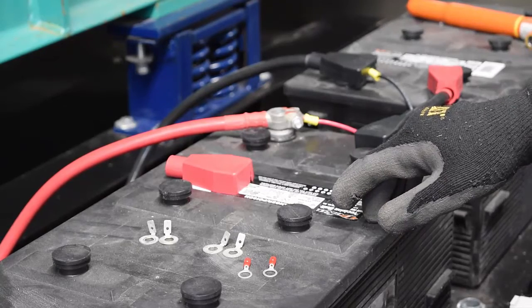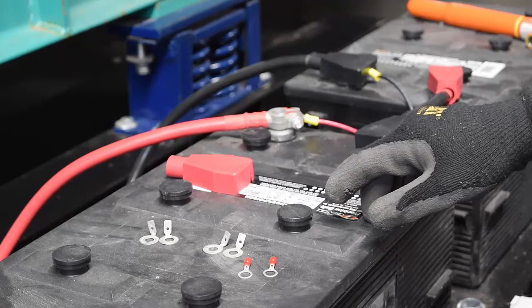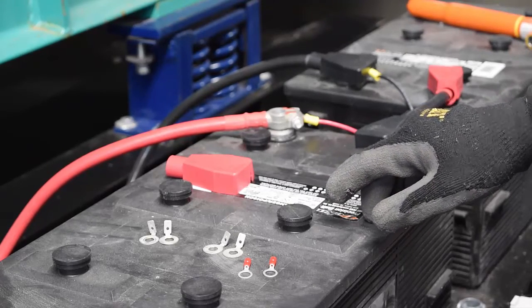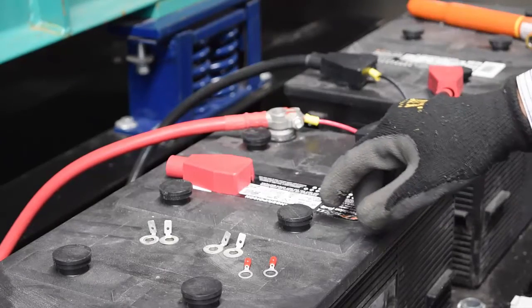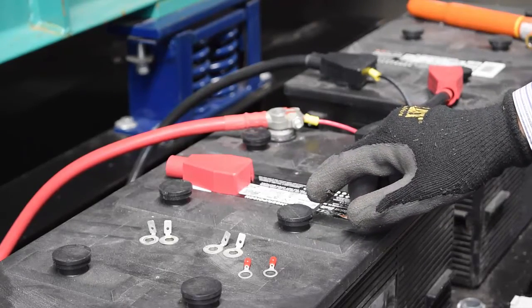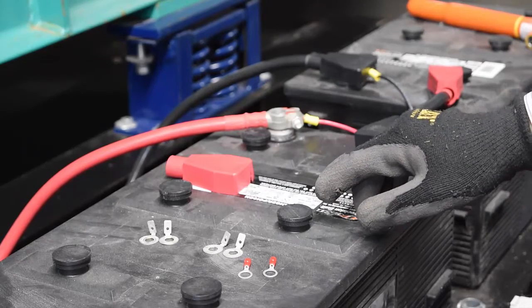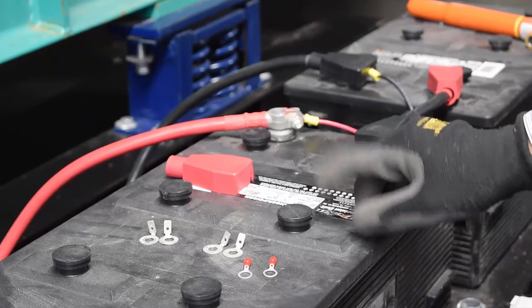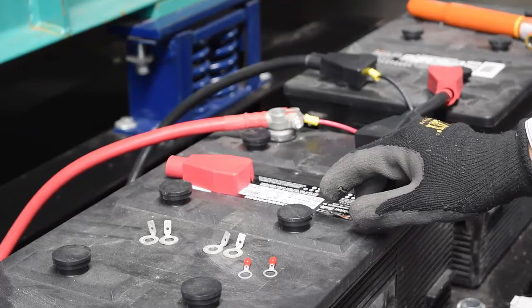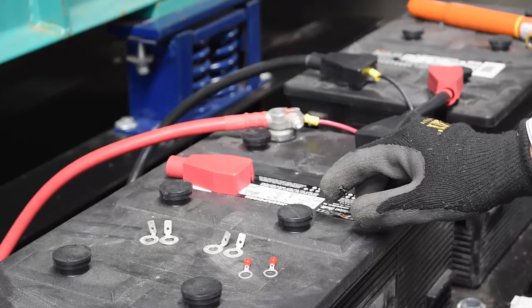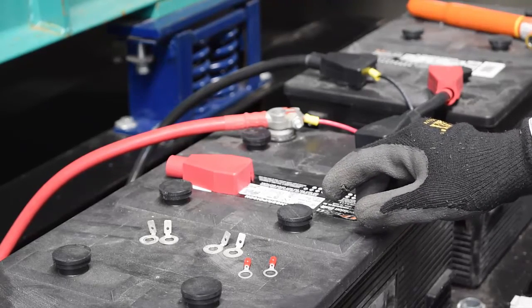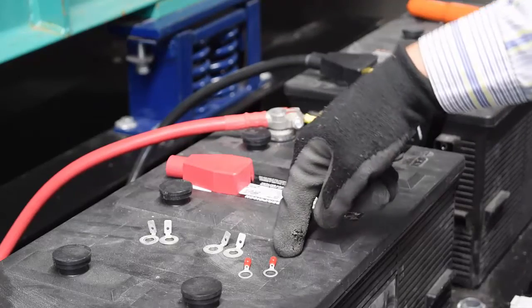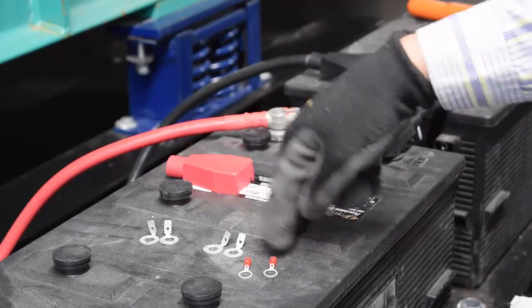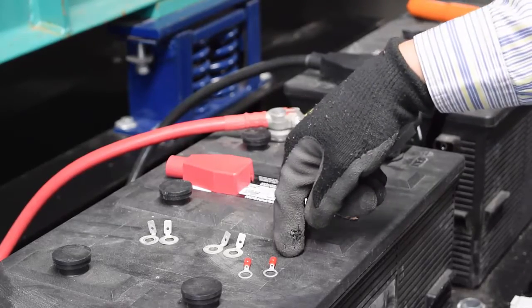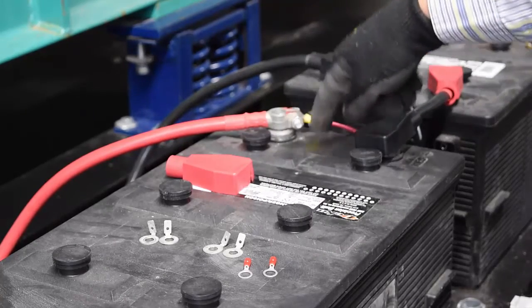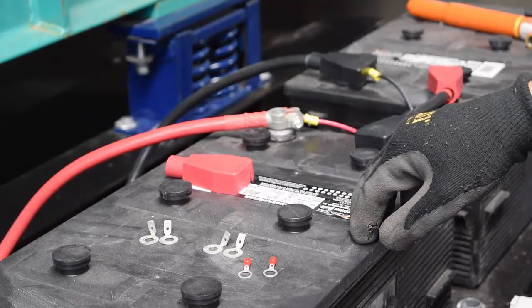If your system includes a BVI module and the string voltage is under 58 volts, another tab washer would be required in the most negative and most positive posts. Finally, if the CellQ1 controller is configured to be powered by the battery string, meaning it's DC powered, then we provide a DC powered kit that includes these ring terminals. And we provide several sizes depending on the size of the post that you can connect to.